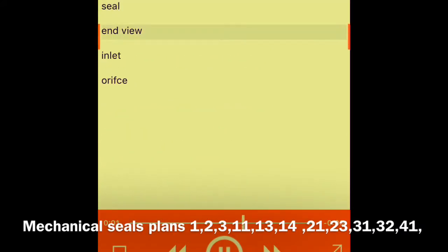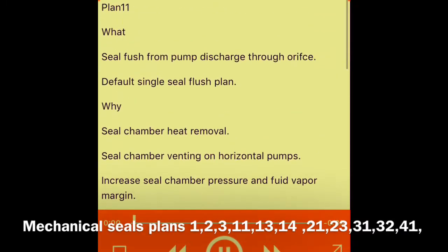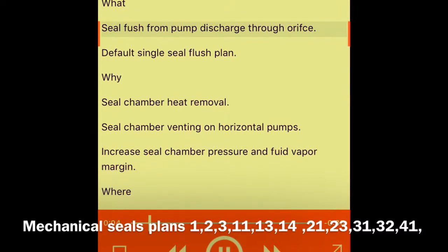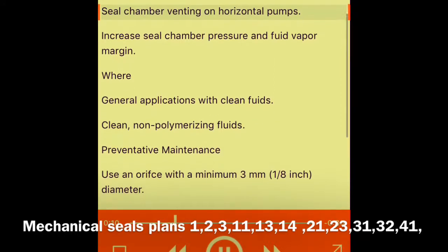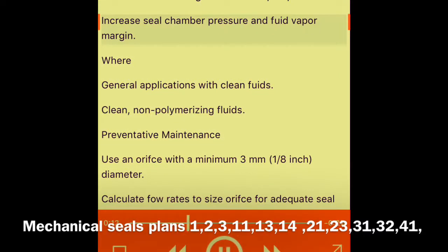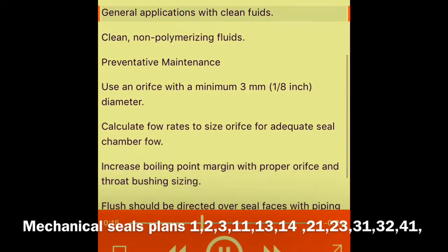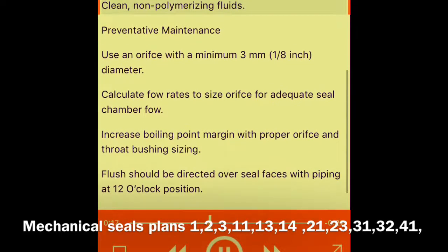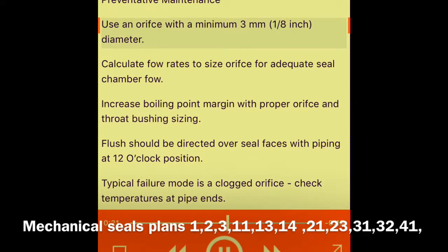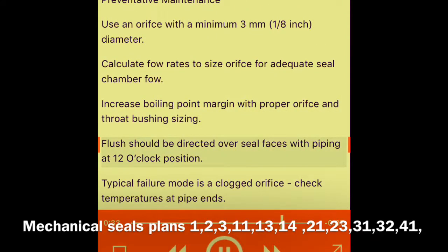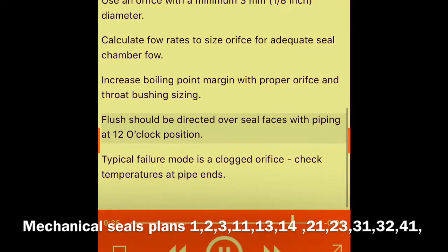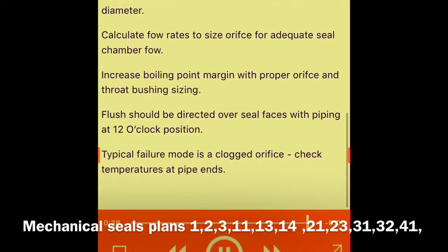Plan 11 — seal end view, inlet orifice. What: seal flush from pump discharge through orifice. Default single seal flush plan. Why: seal chamber heat removal, seal chamber venting on horizontal pumps, increase seal chamber pressure and fluid vapor margin. Where: general applications with clean fluids; clean, non-polymerizing fluids. Preventative maintenance: use inlet orifice with a minimum 3 mm (1/8 inch) diameter; calculate flow rates to size orifice for adequate seal chamber flow; increase boiling point margin with proper orifice and throat bushing sizing; flush should be directed over seal faces with piping at 12 o'clock position. Typical failure mode is a clogged orifice. Check temperatures at pipe ends.